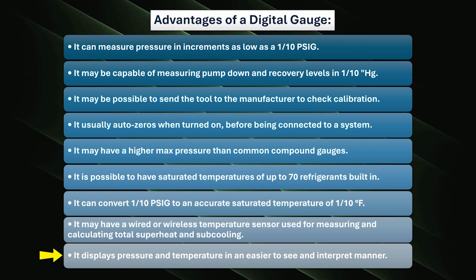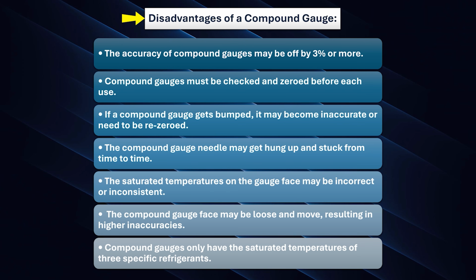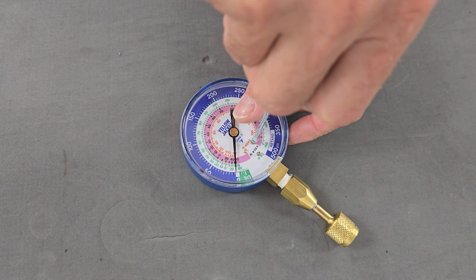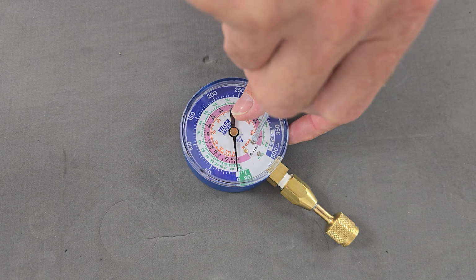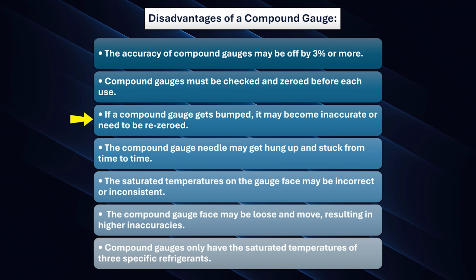It displays pressure and temperature in an easier to see and interpret manner. Disadvantages of a compound gauge. The accuracy of a compound gauge may be off by 3% or more. Compound gauges must be checked and zeroed before each use. If a compound gauge gets bumped, it may become inaccurate or need to be re-zeroed.